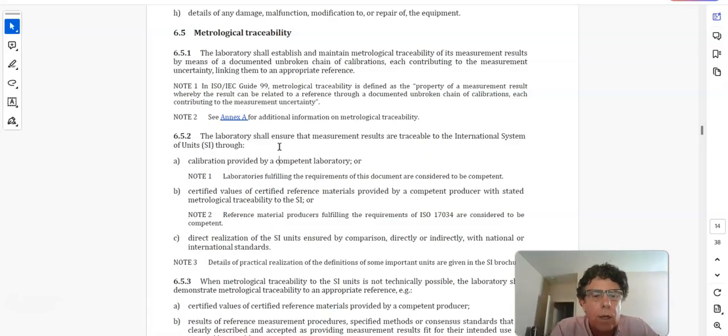But if you did A, you'd probably get away with having a calibration on your balance if you only use your balance once a year. But most labs use their balance more than once a year. So now let's say you decide that you want to use reference weights for your balance once a month. So you check your balance on, today's 5/1/2024.